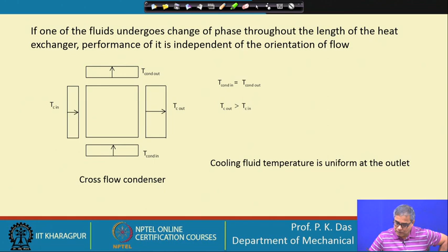Now, let us take up a problem. A condenser is required for an organic vapor having a latent heat of 250 kilojoule per kg flowing at 5 kg per second. The vapor is pure and may be assumed to condense at its saturation temperature of 80 degree Celsius. The condenser is cooled by cooling water, specific heat has been given, with an inlet temperature of 20 degree Celsius and outlet temperature of 35 degree Celsius. The overall heat transfer coefficient has been given. Calculate the cooling water flow rate, the value of delta T and the surface area. What is the F value for this case?